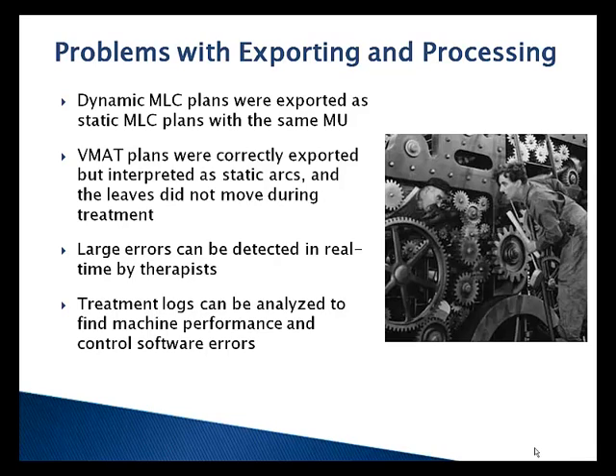One real scary case was a VMAT plan that was sent over correctly. Everything went correctly except the software in the Linac that figures out, is this a VMAT plan or is this a conformal arc where my leaves don't move? The leaf didn't move enough the first 5 or so degrees, and it said, oh, this must be a static arc then. And so the leaves didn't move throughout the treatment. That was a software upgrade that got fixed.